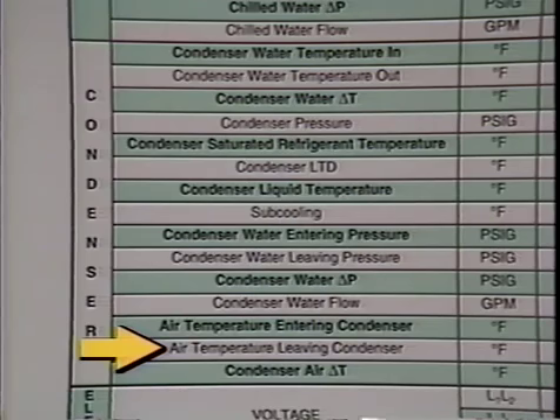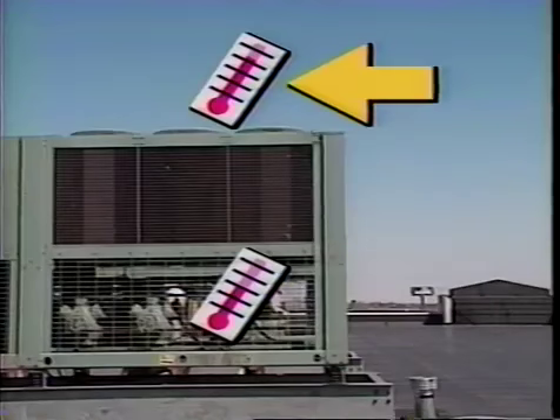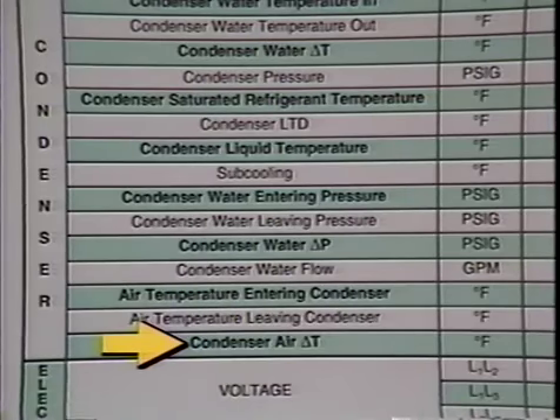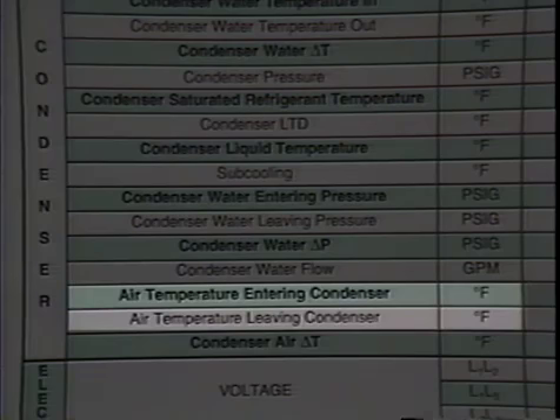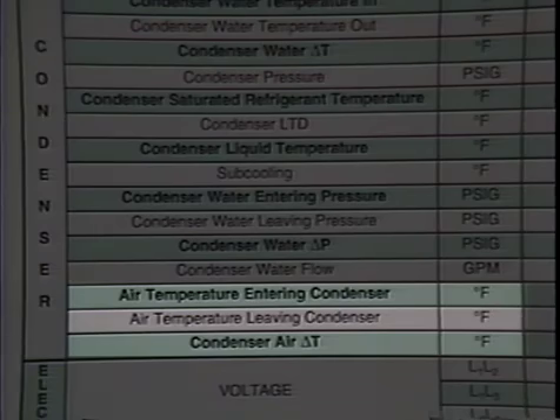Air temperature leaving condenser. For air-cooled condensers, this measurement will be useful in determining temperature rise across the condenser coil. The temperature rise, or delta T, can be determined by subtracting the condenser entering air temperature from the condenser leaving air temperature. The delta T provides an indication of the heat rejection by the condenser.